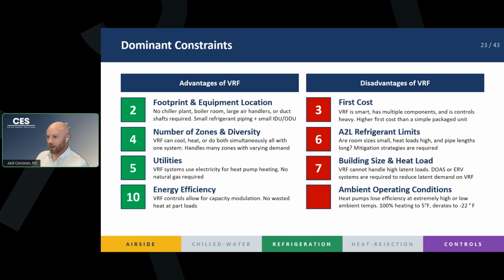Another disadvantage of VRF is building size and heat load, right? This one's more about heat load. I talked a little bit about the dew point and the temperature of the coils. Essentially, these VRF systems are not good at high humidity loads, right? High latent loads are not going to be able to be cooled down by our VRF system. At full loads of our VRF system, we're going to be able to cool that and get rid of the humidity just fine because our coil temp is cold. But if we're running at part load, our coil temperatures creep up and we're not going to be able to remove the moisture. So if you have high latent loads on your project, you have to think about how to counterbalance that with a supplementary system. We're going to usually use a DOAS system or an ERV system to whisk the moisture out of our outside air before it reaches our VRF.